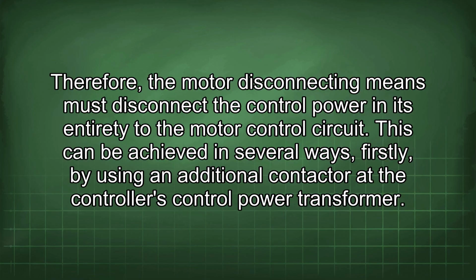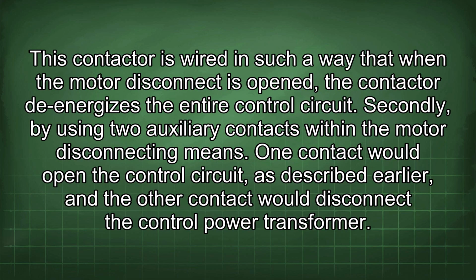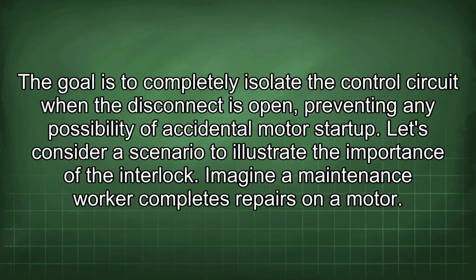This can be achieved in several ways. Firstly, by using an additional contactor at the controller's control power transformer. This contactor is wired in such a way that when the motor disconnect is opened, the contactor de-energizes the entire control circuit. Secondly, by using two auxiliary contacts within the motor disconnecting means. One contact would open the control circuit as described earlier, and the other contact would disconnect the control power transformer. The goal is to completely isolate the control circuit when the disconnect is open, preventing any possibility of accidental motor startup.